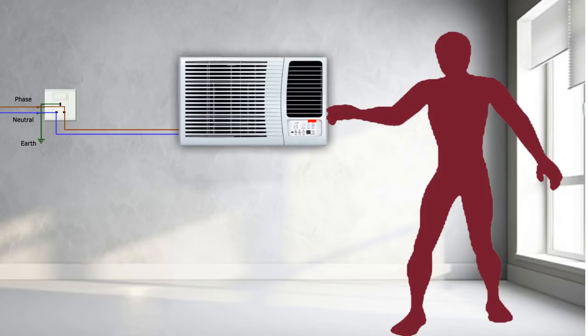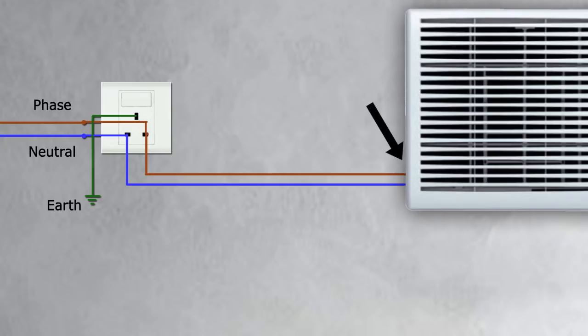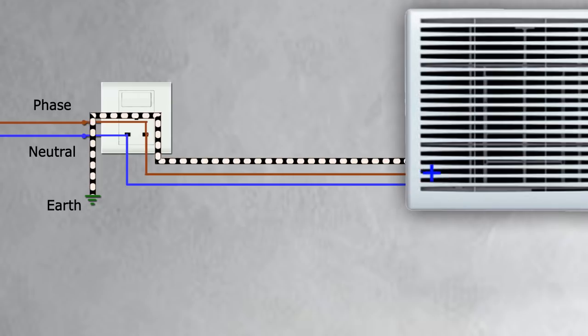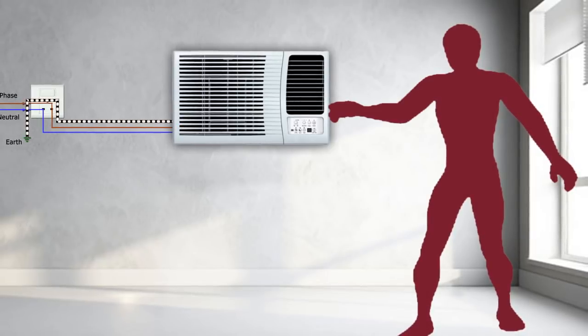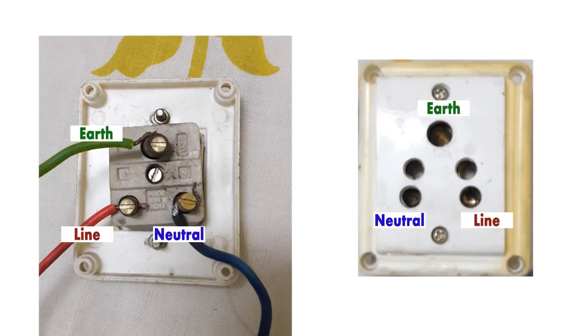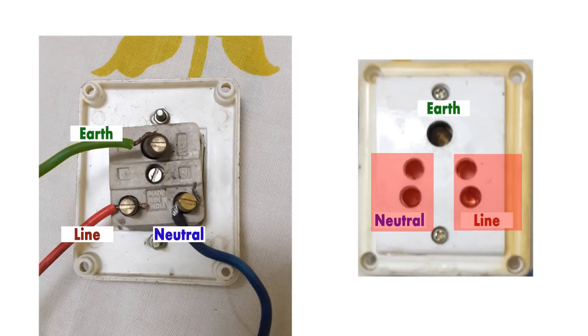To avoid such circumstances, the earth wire should always be connected to the instrument body, so that when leakage happens, the current gets drained directly into the earth and must not flow through the person's body. So during normal working condition, neutral wire works along with line wire to drive our load, whereas earth wire works only in condition of leakage current.